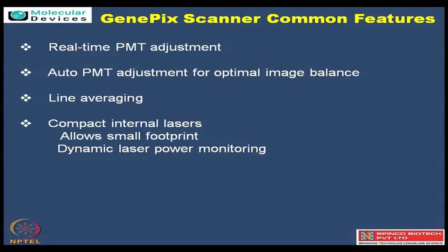PMT - the photomultiplier tube - real-time adjustment means at the level of scanning we can look at the data when scanning is live. In this form we can control the PMT live in between the scan. There is also an auto PMT adjustment for those who are not comfortable with controlling them manually - we have given an auto PMT option which allows Acuity to get the best output. GenePix Pro allows multiple scans by itself, so the best PMT suitable for one application can then be seen immediately.